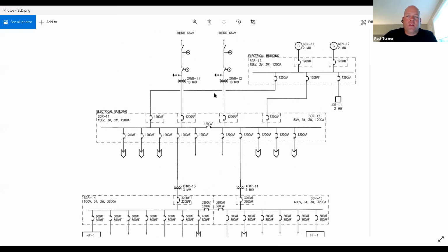Following that 24-hour soak period, you can then close one of the breakers for switchgear 11 to energize this 15 kV bus. In this system, there's a tiebreaker between switchgear 11 and switchgear 12. That tiebreaker would remain open while the two utility feeds are closed. Your switchgear would typically have interlocks in the system to guarantee that when the two utility feed breakers are closed, the tiebreaker is interlocked and remains open. Those interlocks would have been tested before energizing from the utility. So that energizes the 15 kV bus of both switchgear 11 and switchgear 12.